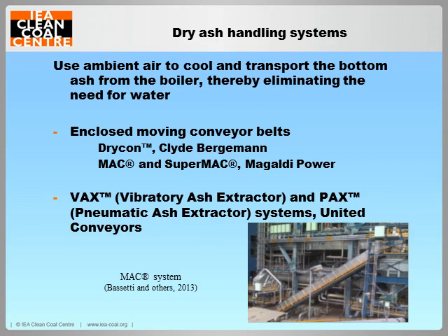Dry ash systems use ambient air to cool and transport the bottom ash from the boiler, thereby eliminating the need for water. Several approaches have been developed. Now, in some systems, the bottom ash from the boiler falls onto an enclosed moving conveyor belt. The negative pressure in the boiler draws in ambient air, which moves in a counterflow direction over the ash. Sensible heat from the ash is transferred to the air, which is returned to the boiler as preheated air for combustion. And this actually improves the thermal efficiency of the boiler.